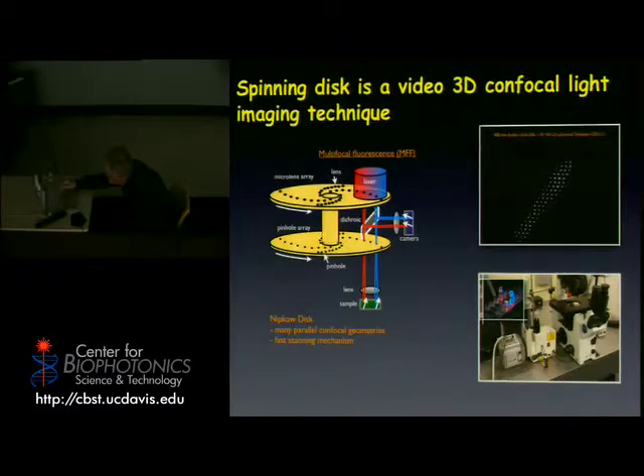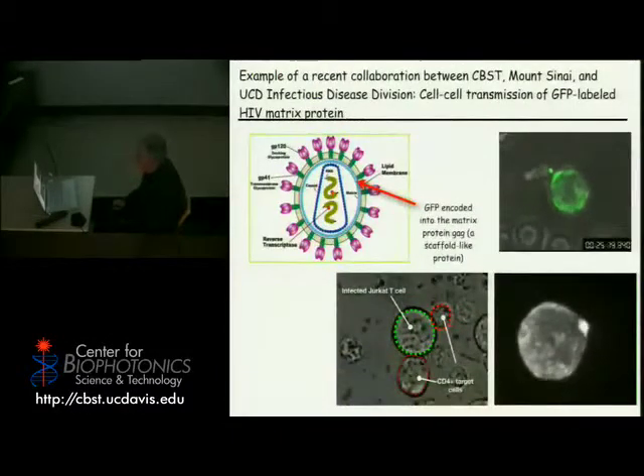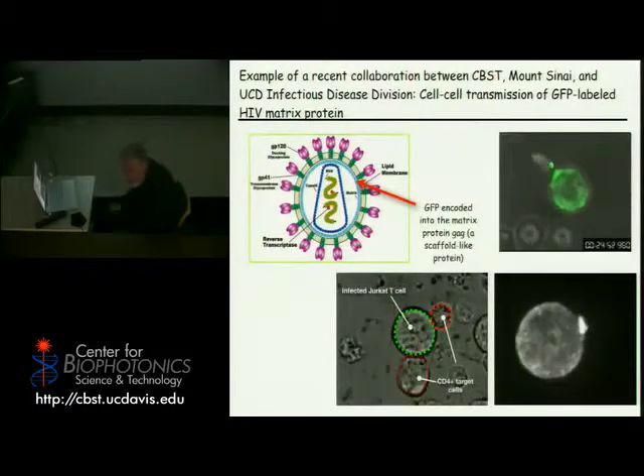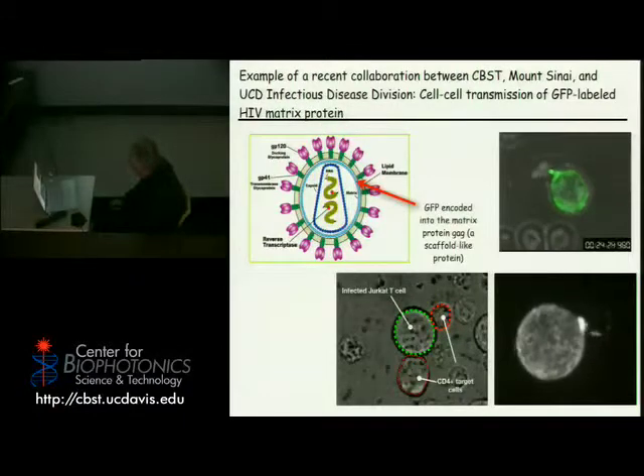One problem with that technique is you have to scan a single pinhole back and forth, which takes quite a bit of time. A way of automating that is using multiple pinholes on a spinning disk — each pinhole collects light for a portion of the image, the disk spins to scan the whole image, and instead of a single detector you use a camera. Using this spinning disk microscope, you can collect 3D movies.